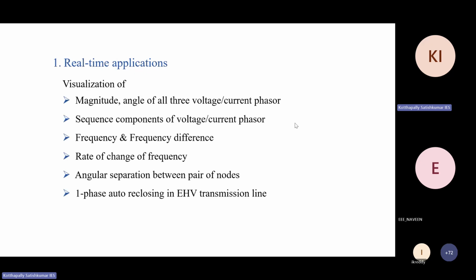You can visualize the magnitude and angle of all the 3-phase currents and voltages. Another thing you can visualize is the sequence components of voltages, frequency difference, rate of change of frequency, angular separation between the nodes as I explained earlier, and single phase auto reclosing on EHV transmission lines. These are just the major things which I need to explain. There are many things you can visualize, because once you have the voltage, the current and the phase angle, you can calculate anything from these 3 components.